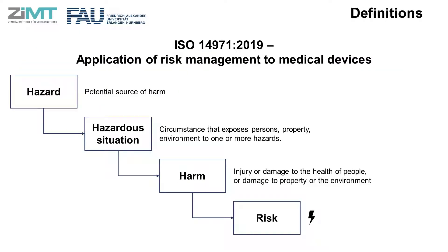The requirements set out in the MDR are best understood in the context of ISO 14971:2019, Application of Risk Management to Medical Devices. This international standard is accepted as the standard for meeting MDR requirements and outlines in detail risk management for the specific context of medical devices.